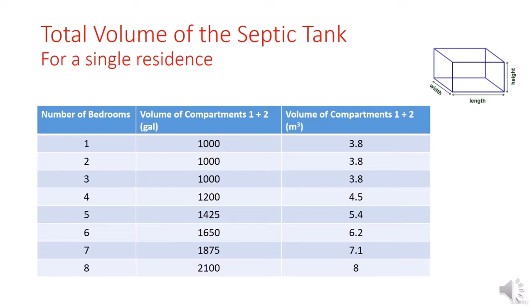Let's see what is the total volume of the sedimentation tanks when designing a wastewater treatment plant for a single residence or one house. The volume is width times length times height. As you can notice from the table, the total volume of both the first and second sedimentation tanks is based on the number of bedrooms. The minimum volume is 1,000 gallons or 3.8 cubic meters, which applies for up to three bedrooms. As the number of bedrooms increases, the volume will also increase.